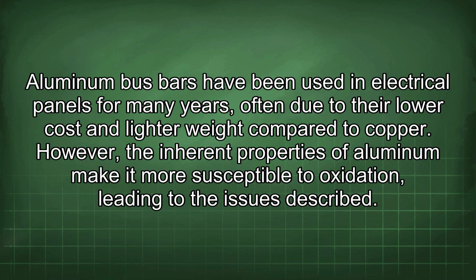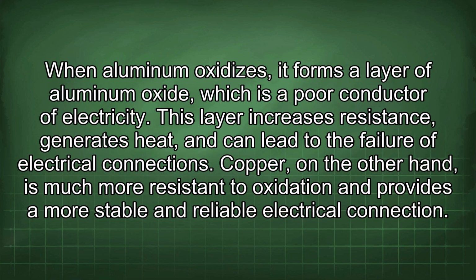However, the inherent properties of aluminum make it more susceptible to oxidation, leading to the issues described. When aluminum oxidizes, it forms a layer of aluminum oxide, which is a poor conductor of electricity. This layer increases resistance, generates heat, and can lead to the failure of electrical connections. Copper, on the other hand, is much more resistant to oxidation and provides a more stable and reliable electrical connection.